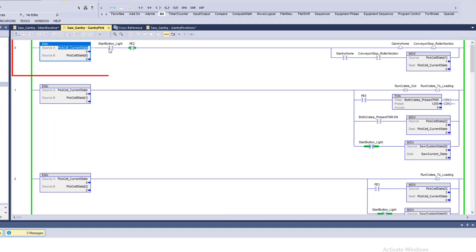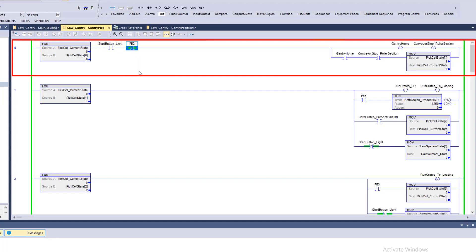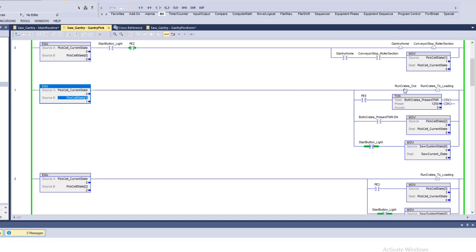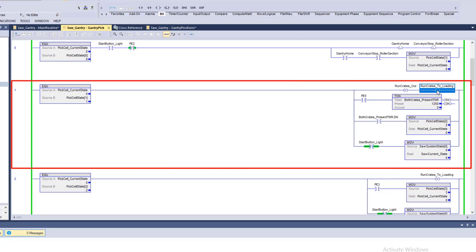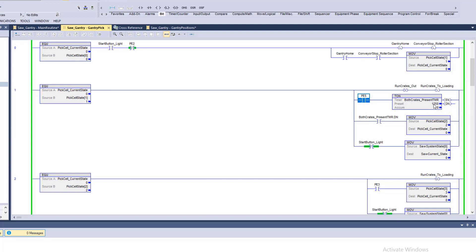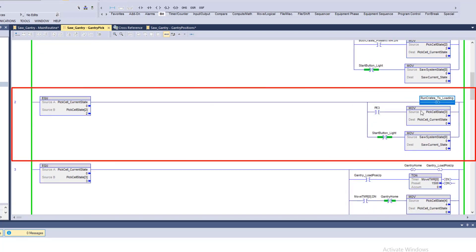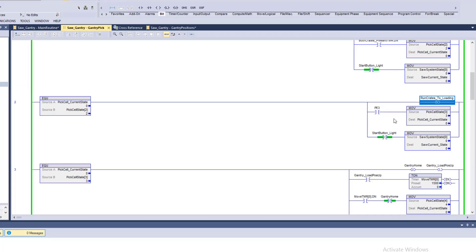For the gantry pick state machine: in state zero, if the machine is not active or PE2 is not active, it homes the gantry and raises the crate stops. Once that's done it goes into state one, unlatches the crate run-out, and runs crates in. When crates run into PE5 and both crates are present for a second and a quarter, it goes into state two, which unlatches crates loading — stopping and stationing the crates. When product is present it moves to state three.